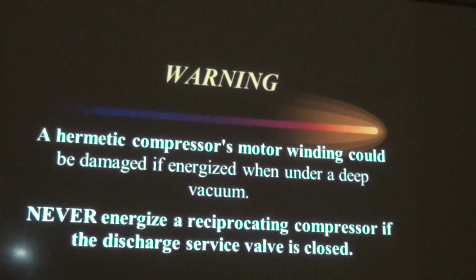And again, it reminds us that hermetic compressors, sealed dome compressors, are all cooled by using the suction line refrigerant vapor. So in an R22 system, 69 PSI means that we're pulling refrigerant into that canister. That's about 50 degrees with the superheat.